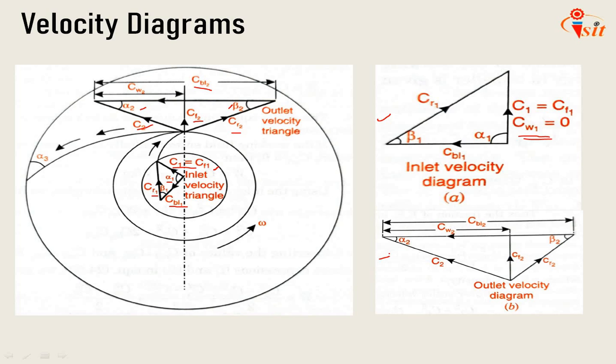Therefore alpha 2 is the diffuser blade angle at the inlet and alpha 3 is the diffuser blade angle at the outlet. If the discharge from the diffuser is circumferential, then its blade angle at outlet should be as small as possible. So generally alpha 3 we are not considering, it is negligible.